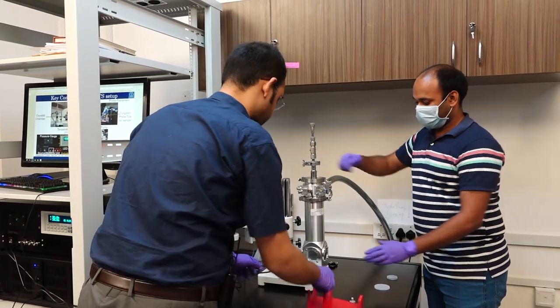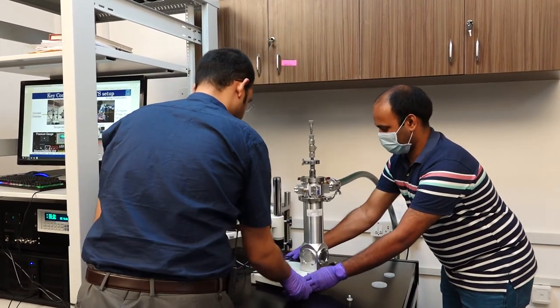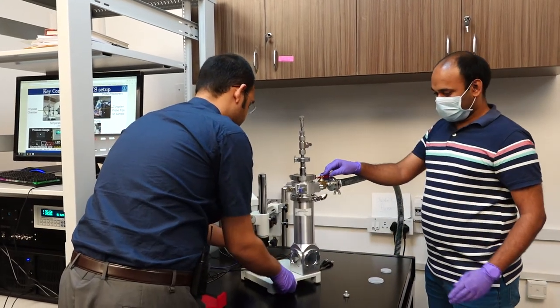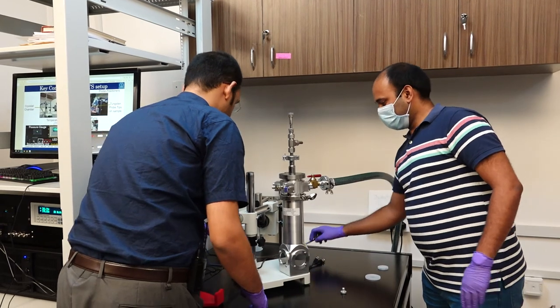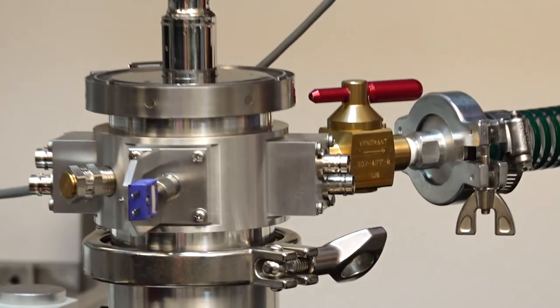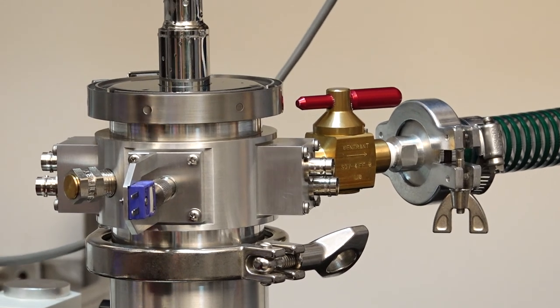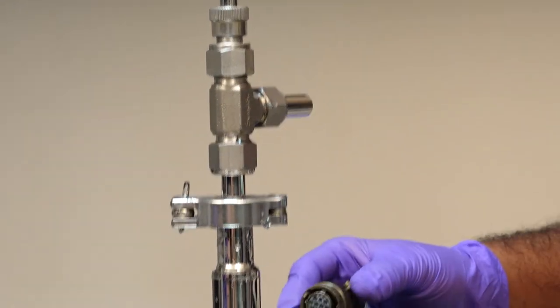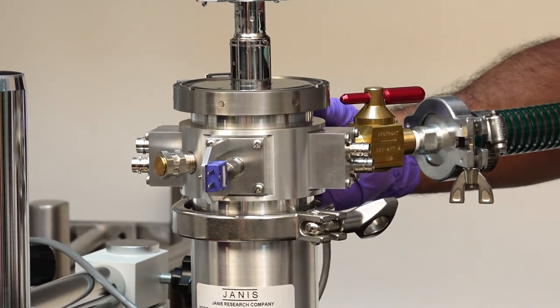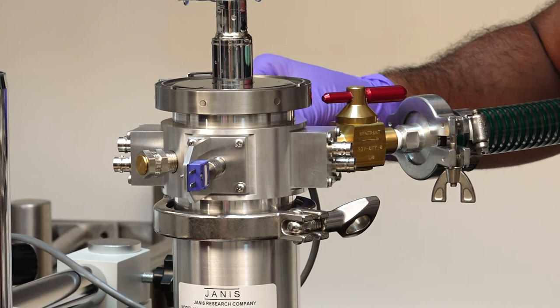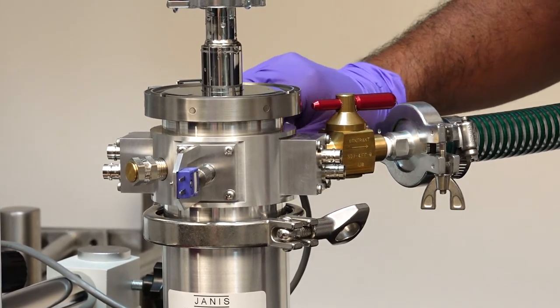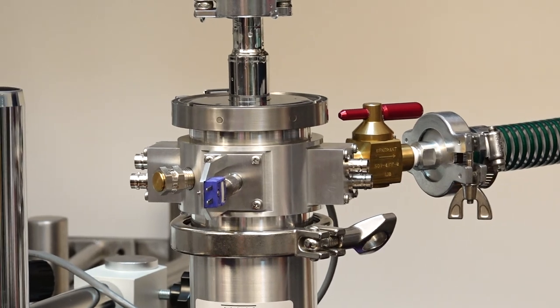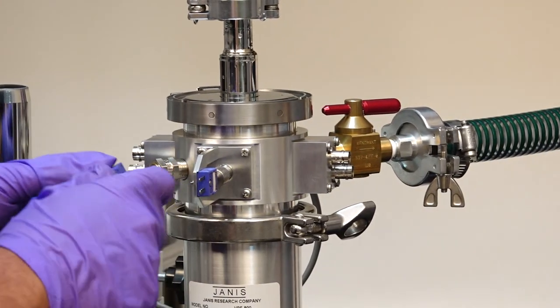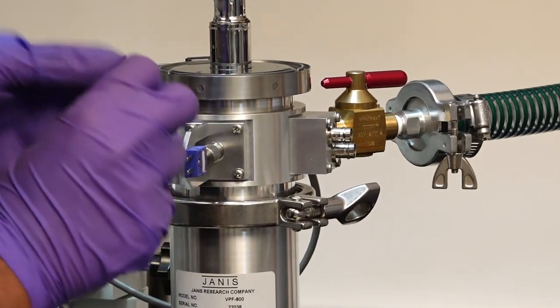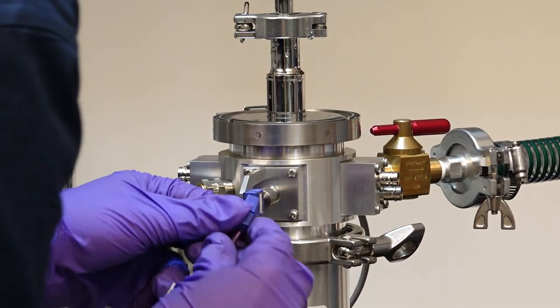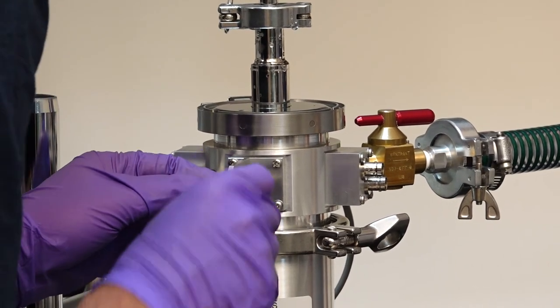A few more things have to be connected before we start off with the measurements. First is this temperature controller gauge, which has to be rotated in slowly. Next is the thermocouple sensor port. We have to check for the sign, so there is plus and minus; we have to match the signs and then just plug it in.